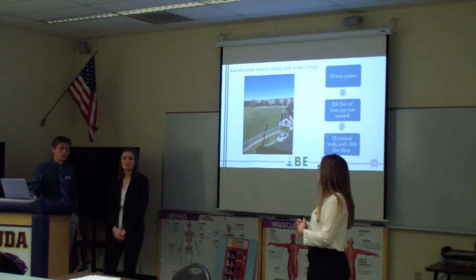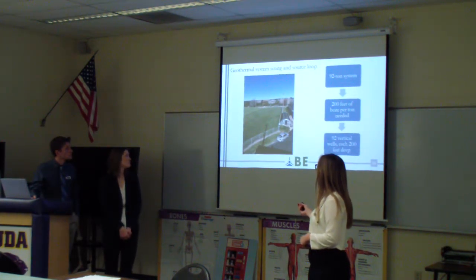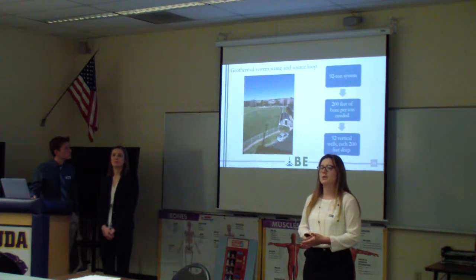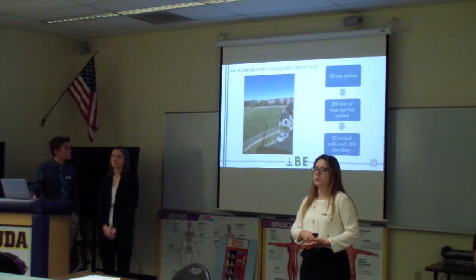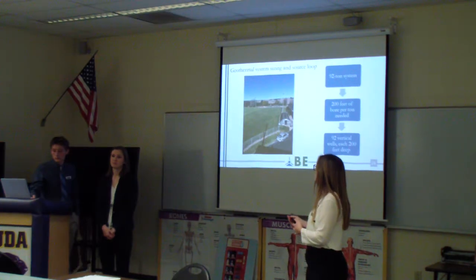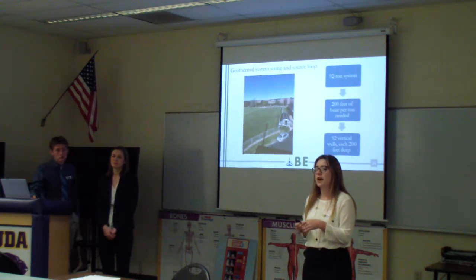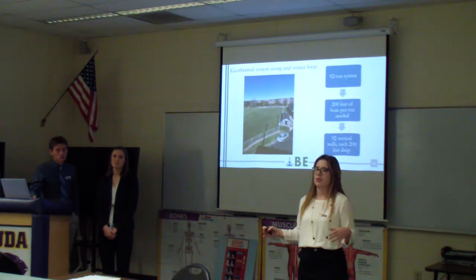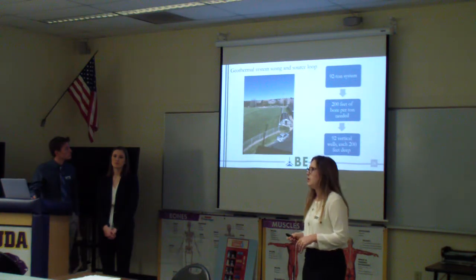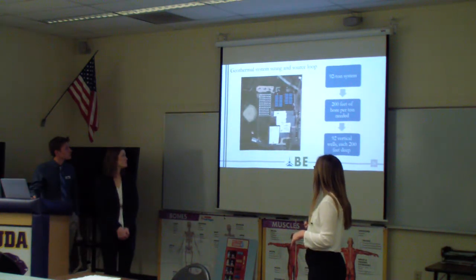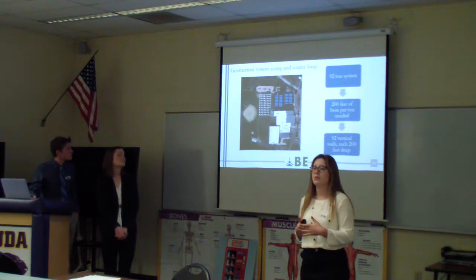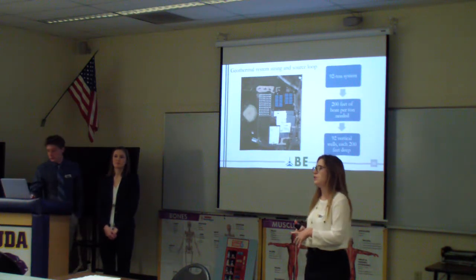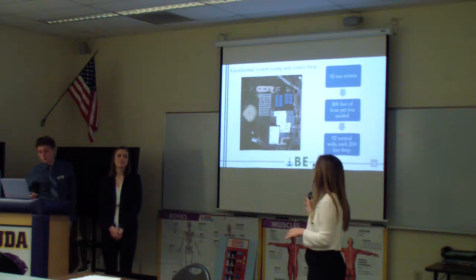We are proposing to place the source loop underneath the outfield of the existing baseball diamond on the west side of the school. And a horizontal loop was considered, but there's not enough available space on the school property to support such a large system. Therefore, BECO is instead recommending a grid system of 92 vertical wells, each 200 feet deep, as seen here.